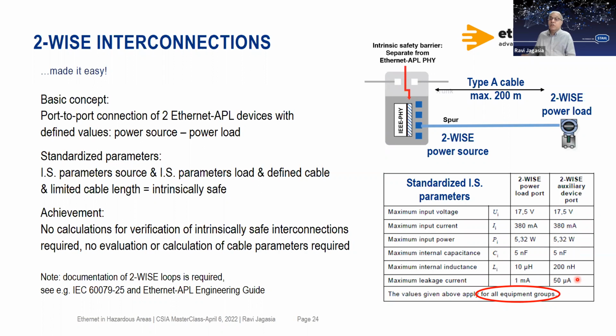Remember one thing that you still need to document, because recording those entity parameters is required. Sorry for that mix up on the words. It is required under 60079-25 and also under NEC 500 and OSHA guidelines, because we do need to do change management. We need to record what are the field devices we connect to those switches, and those are then recorded from the perspective of maintaining the history in terms of changes that you would do in the future when you're repairing or replacing. Reduces your engineering design time, reduces your deployment time, but record is definitely a requirement which you would need to do.